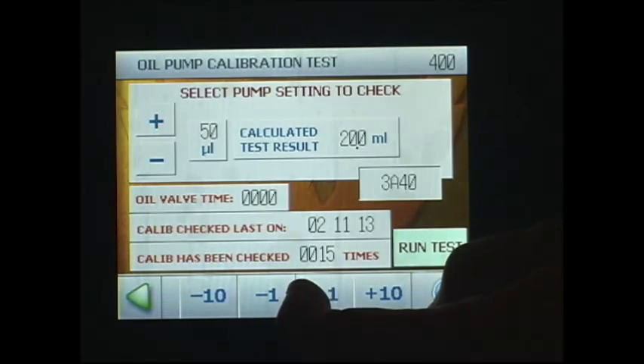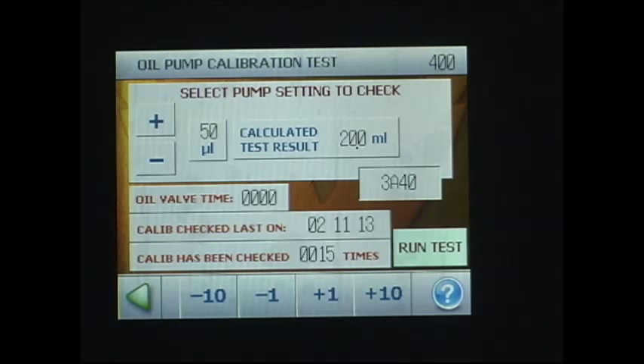Oil pump calibration and adjustment. Upon getting the machine, you'll want to come in here and run this to get the air out of the lines. You can watch your oil pressure gauge. The oil brand that you're using and the viscosity of that oil will dictate the oil pressure. And also the weather. The colder it is, the higher that oil pressure is going to be.